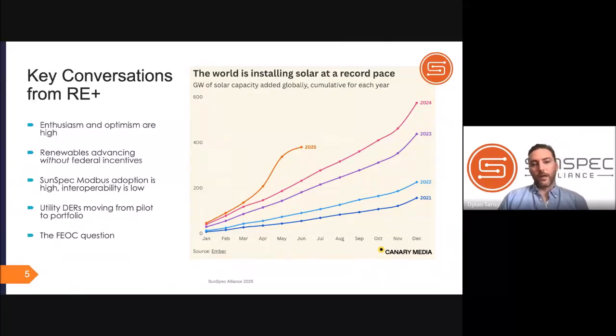Unfortunately, despite a high level of adoption, interoperability is still low. We see this when speaking with integrators who lament having to do customization work to integrate different equipment into their systems. We know through lab testing that the cause is that UL 1741 SB testing alone does a poor job of protocol validation. Since that's just the checkbox needed to get onto the approved equipment list, many device manufacturers leave it at that and haven't gone through the additional steps of full protocol validation. At SunSpec, we have the infrastructure, tools, and support to help the industry get over this hurdle and truly become interoperable.